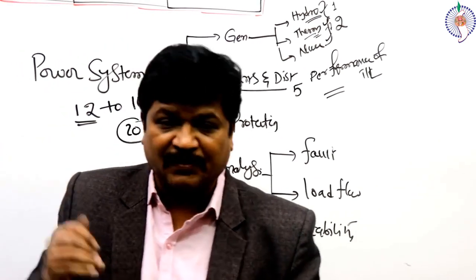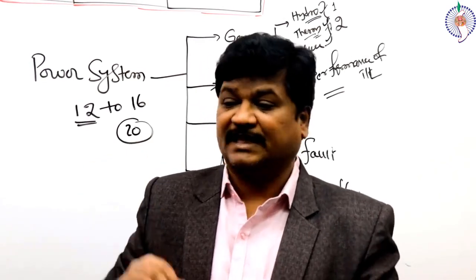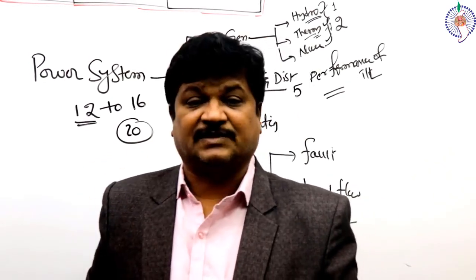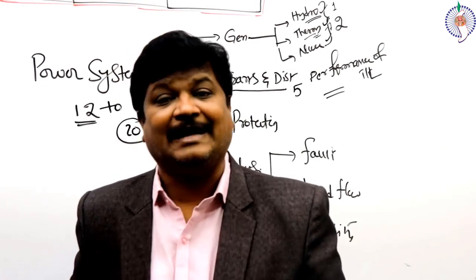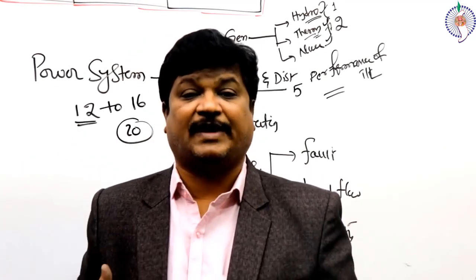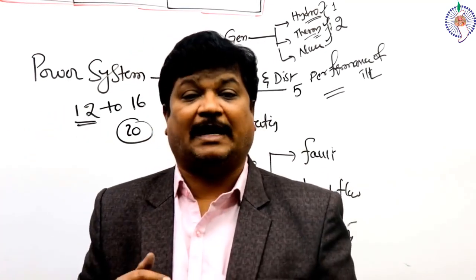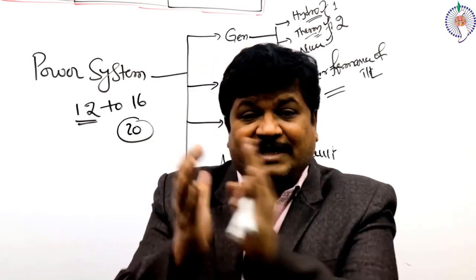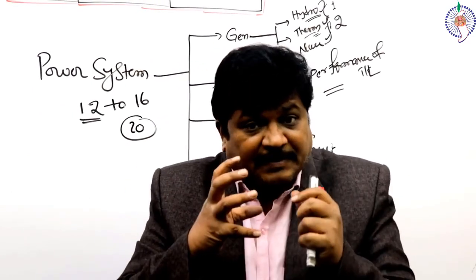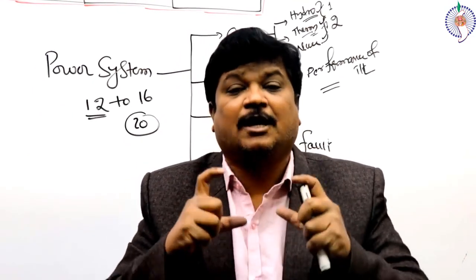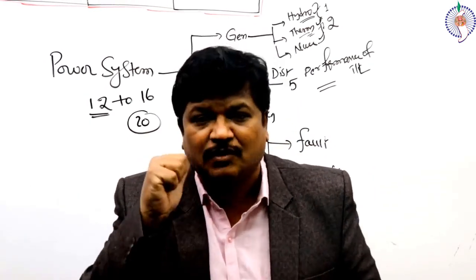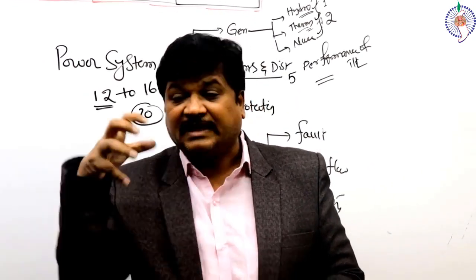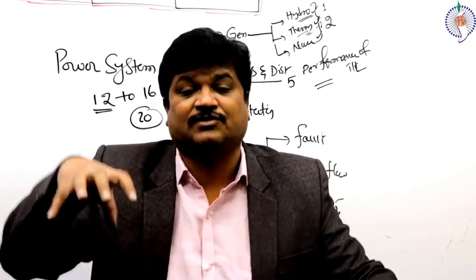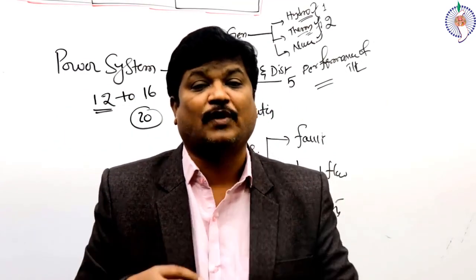Afterwards we have insulators - disc insulators, suspension insulators, applications. For example, if you go for a 220 kV line, what is the type of insulator we are using? How many discs are required? If your line is crossing, what type of insulator? Sometimes they will ask special questions like about post insulators - where we are using post insulators, what is the difference between pin insulator and post insulator? These things we should know.